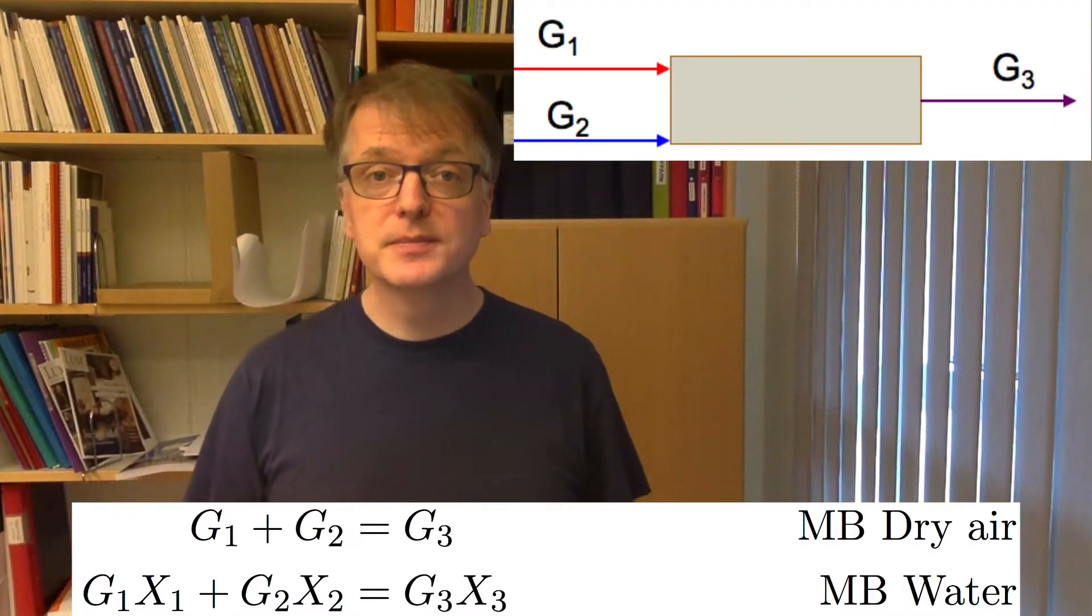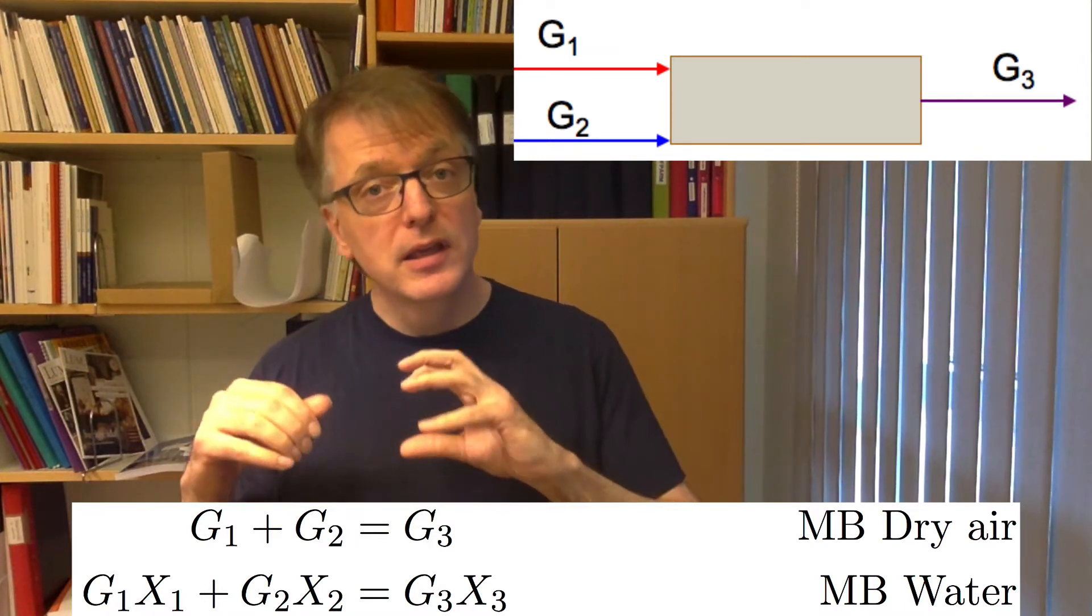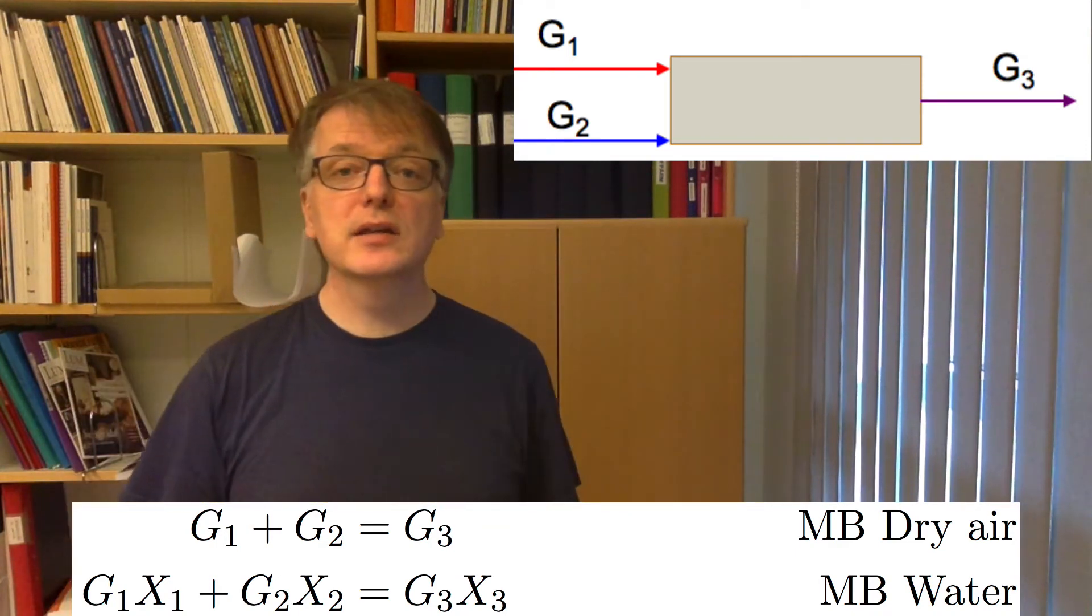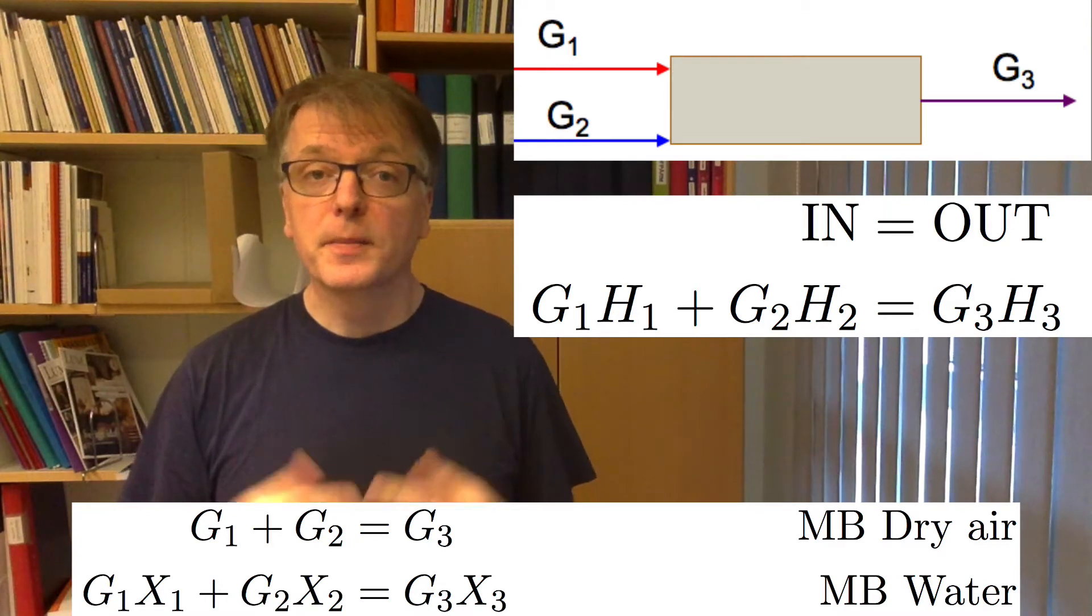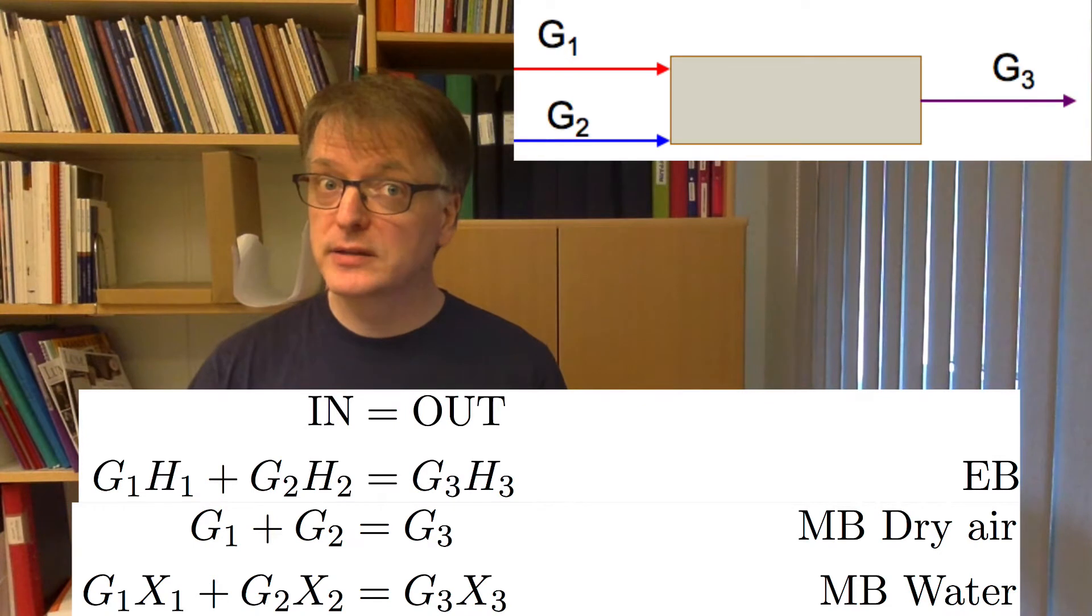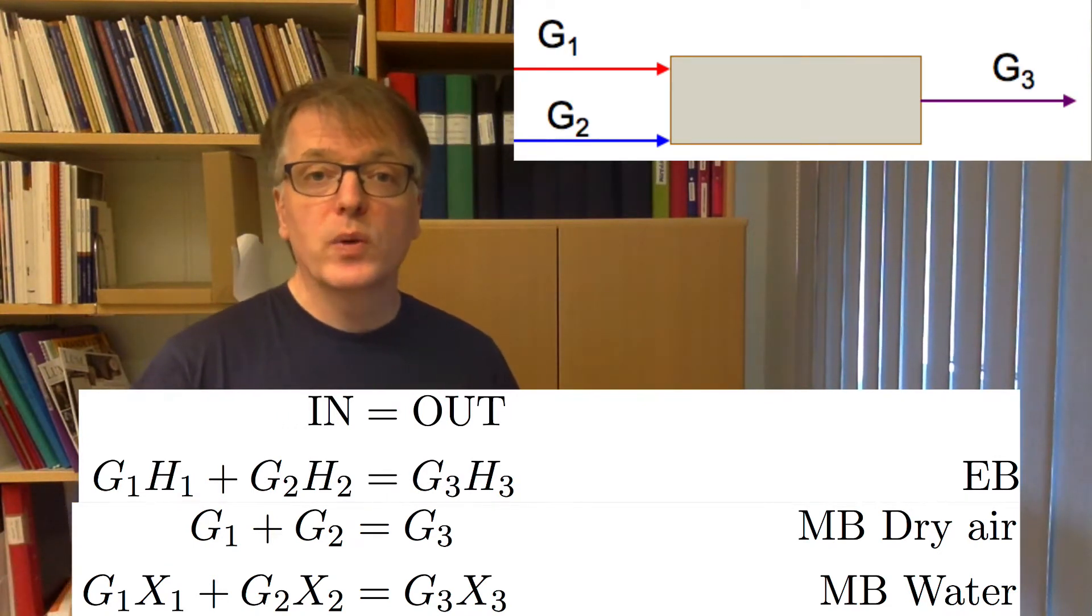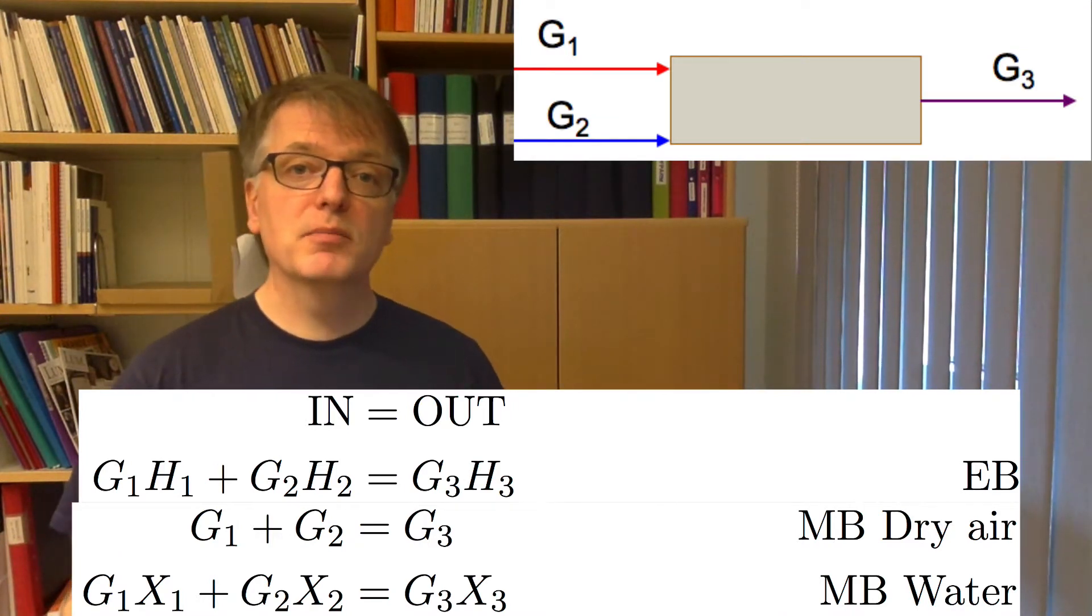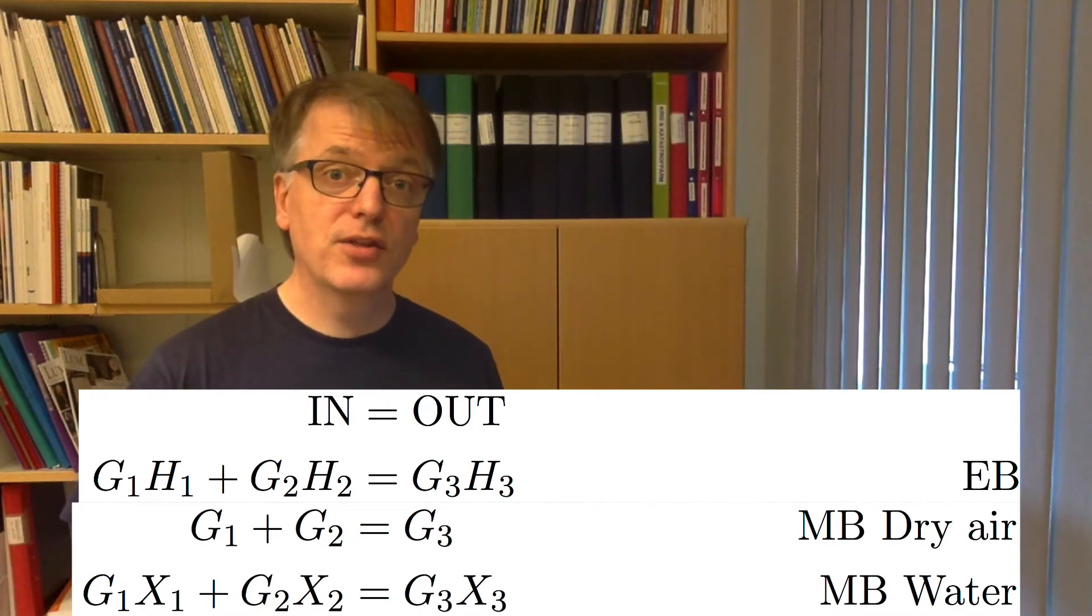What about the energy balance? Well we express the enthalpy h as kilojoules per kilogram of dry air. So if you multiply h with g you get kilojoules per second and that's a good unit for energy balance. Never use temperature as an energy balance unit because that simply doesn't work. So what does the energy balance become? Well it's simply g1 times h1 plus g2 times h2 equals g3 times h3.